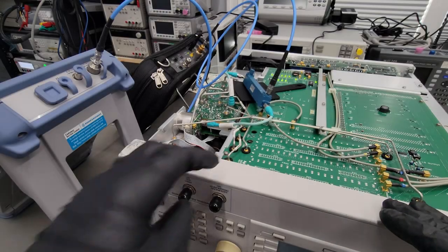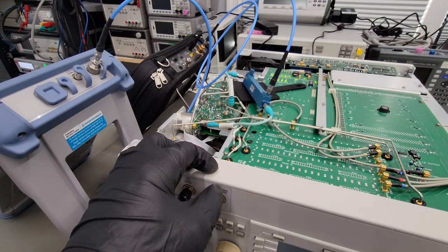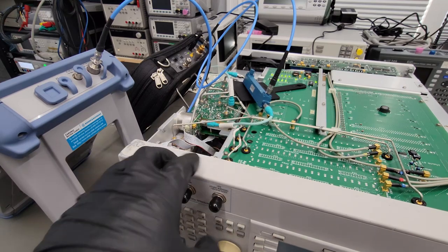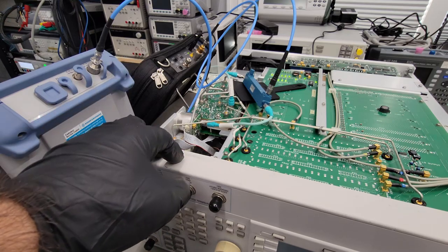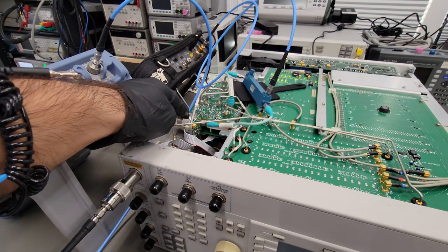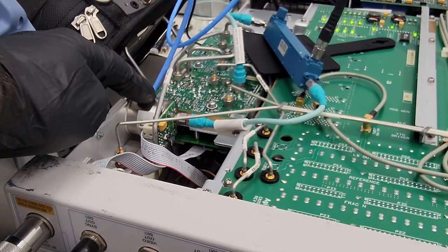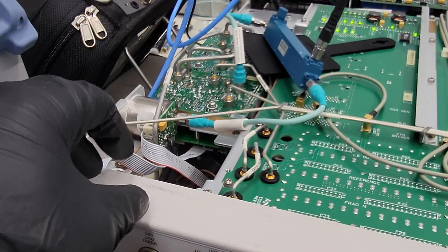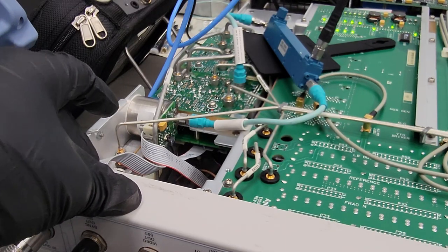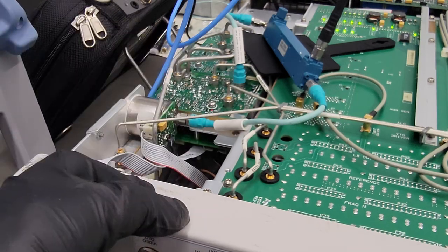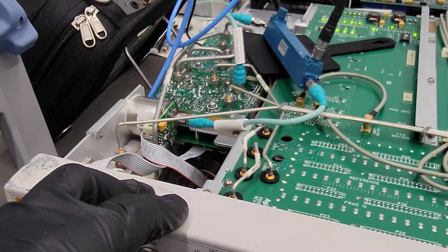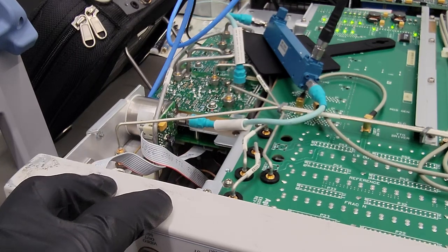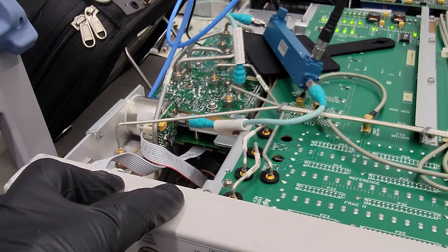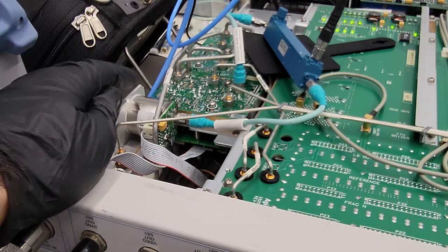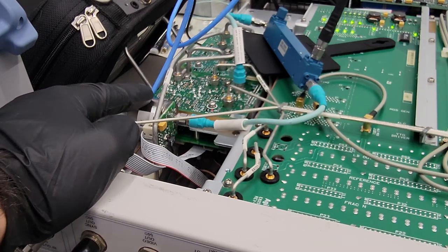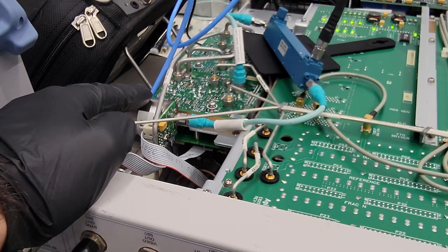So the E8257D is a YIG-based synthesizer, and what that means is that the signal source for the RF output is generated by a YIG-tuned oscillator, and that YIG-tuned oscillator is this device here. So this little cylinder is the YIG, and it tunes from a fundamental frequency between 3.2 to 10 gigahertz. So this PSG, of course, has an analog bandwidth ranging from 100 kilohertz all the way to 20 gigahertz. And the way this instrument synthesizes those frequencies to the output is to take the output from the YIG, which can only tune between 3.2 to 10 gig, and for lower frequencies, it'll divide.